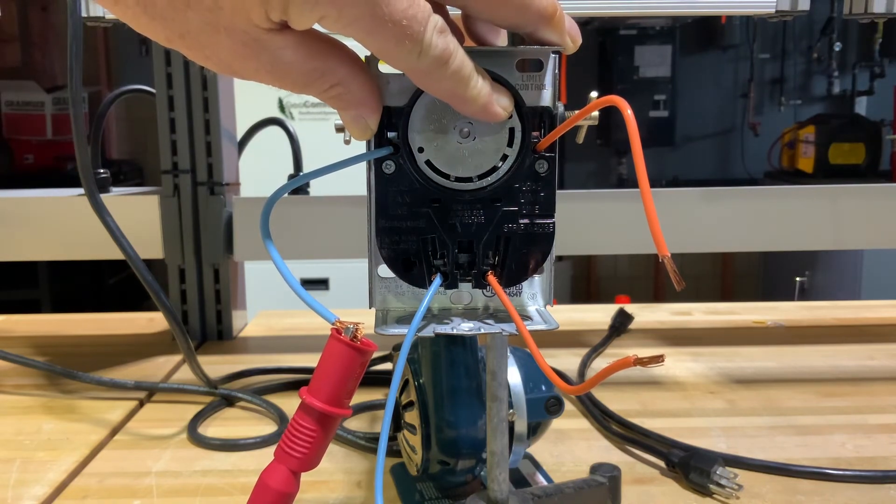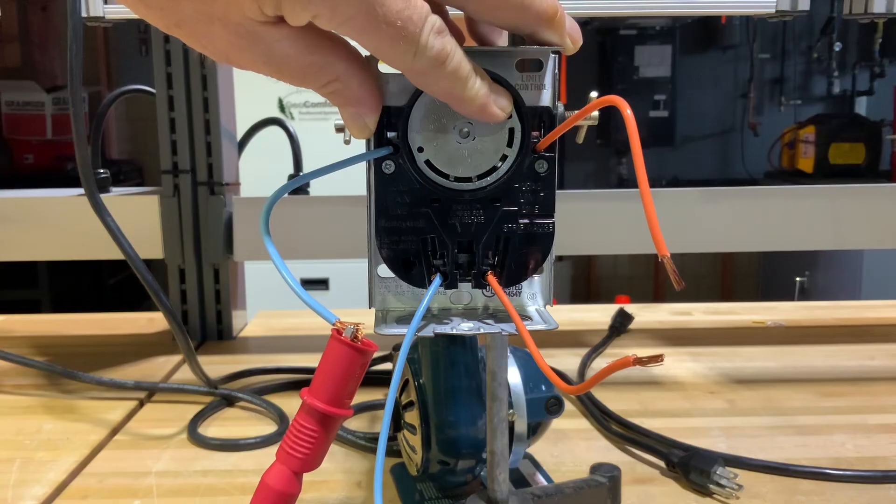Must have been just a delay there, but if I turn this back, cool it off just a little bit more, you can see how that continuity opens up and the fan shuts off.